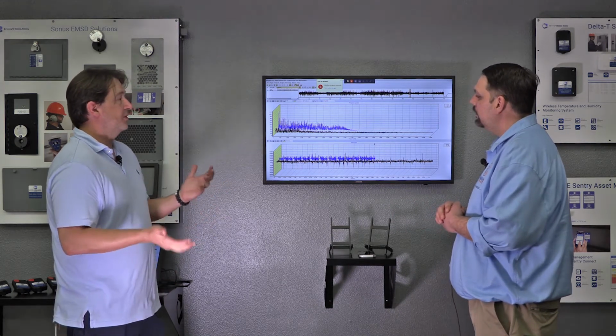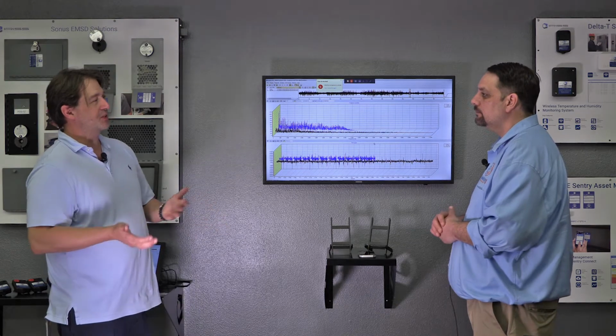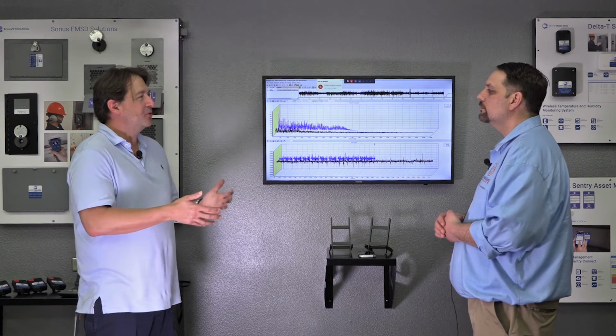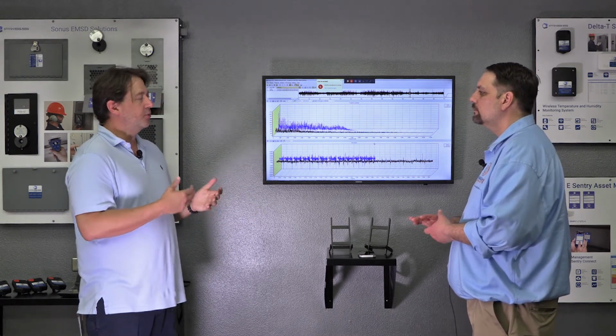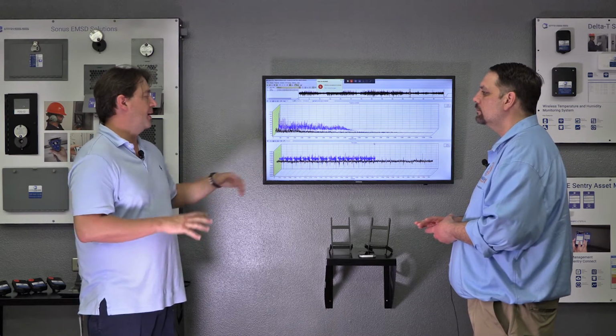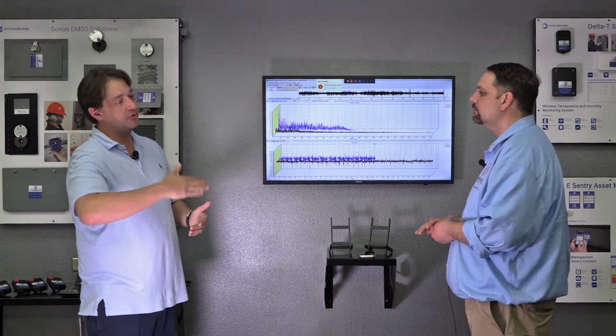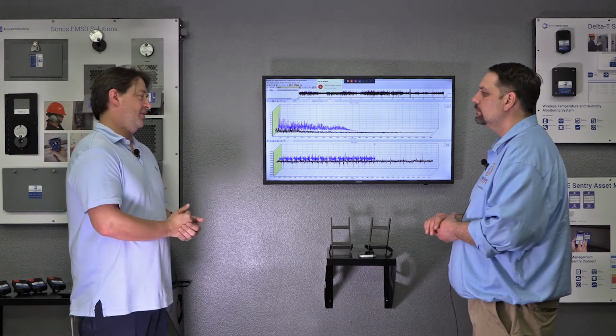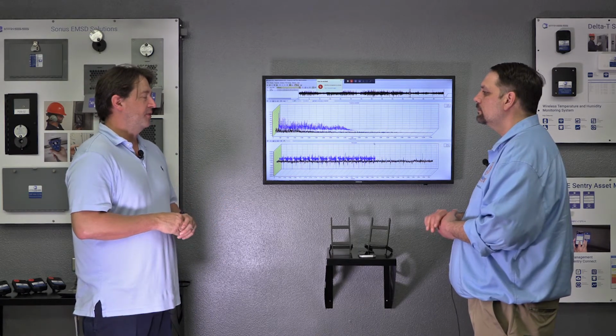Yeah, and this has been the bane of existence for years for electrical inspection with ultrasound: we can't really trend decibels. There's no progression of failure like there is with a bearing. So we were always kind of shoving it off to, I hear something. Then 10, 15 years ago, somebody made a device with ultrasound recording capability. And then it was still kind of like, well, the image looks like this. Now, being able to overlay these in both formats, being able to start marking harmonics out to a millionth of a second, we can get very specific very quickly on what the fault actually is.